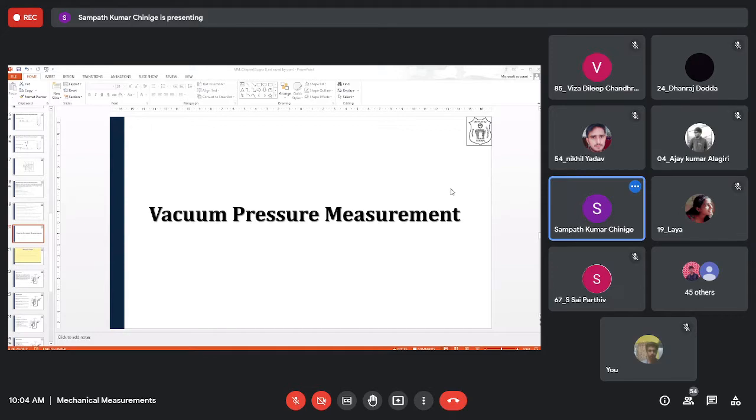Leveling of the instrument is so important. If you are not leveling it perfectly horizontally, there is bound to be some error creeping into the pressure measurement. Then there is tare force, which is basically force error in the determination of the mass of the weights. If you are not properly measuring the mass of the weights, and not taking care of the piston, cylinder, and carrier weight, which are known characteristics of the dead weight tester, then whatever error comes into the force represents the tare force.